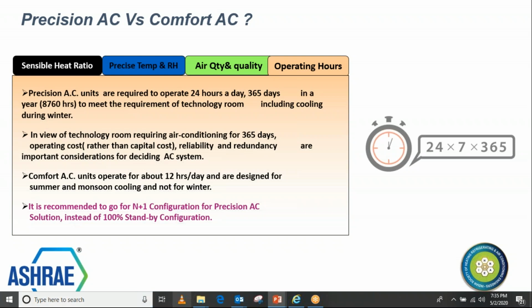Now, on the operating hours, this is a very important aspect, other than the 3 points which we majorly touched before. The operating hours make a difference, because of the design point of all comfort air conditioning systems. You talk about the cabinet construction, the components used, right from the compressor to the expansion valve. The comfort air conditioner may come with a capillary tube, and then the electronics, what kind of electrical and electronics makes are used in the units. You see the control scheme, the controller, and each and every component used in precision air conditioning systems are basically designed to operate 8760 hours and deliver a life of more than 10 to 12 years. So this is the kind of life expectancy you get from the precision air conditioning system compared to the comfort system.